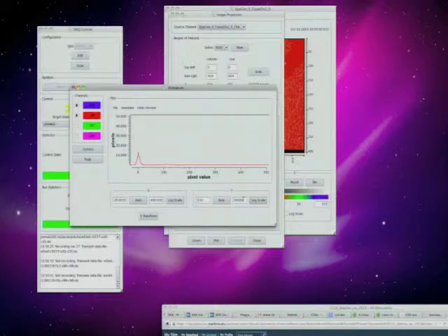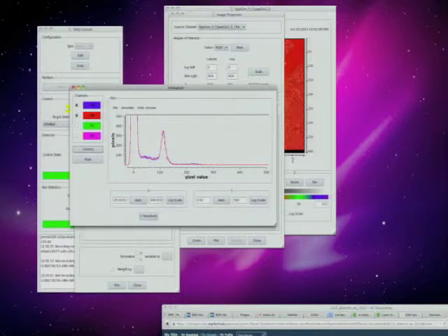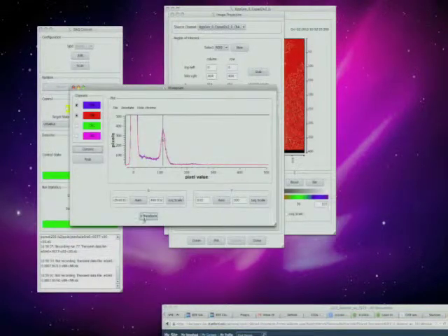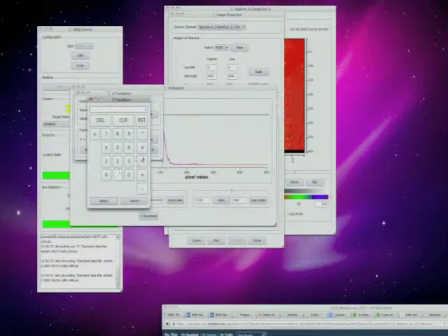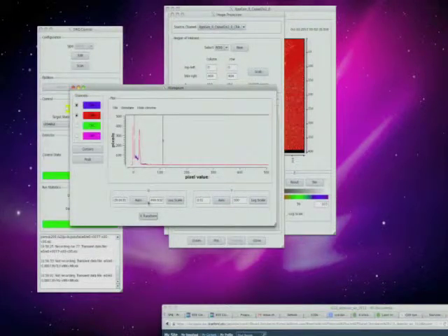So we can take that, much easier in this scale. So we take the cursor. We make grab and something here. That's 111, the peak position. Good enough. It's not a spectroscopic detector. Enter. So it is X divided by 111 multiplied with 22 keV. Apply. Okay. So now we have the scale in keV energy.